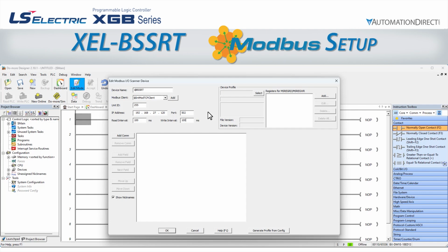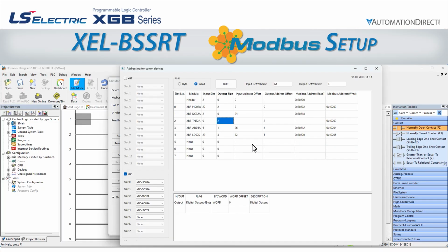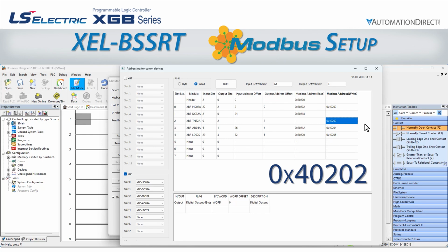We are now ready to add some communication information for this Modbus connection. We will select Add COM and Do More Designer will add a communication block for us. To figure out our Modbus registers, we need to go to our data addressing software tool. We set this up in the previous video on BSSRT data addressing, so please refer to it for further details. When we pull it up, we see that for our setup, the TN32A output module that we want to control is in slot 2, and the data will be at a Modbus write address of 0x40202. For Modbus, 0x4 will be a holding register, which is able to be read from or written to.